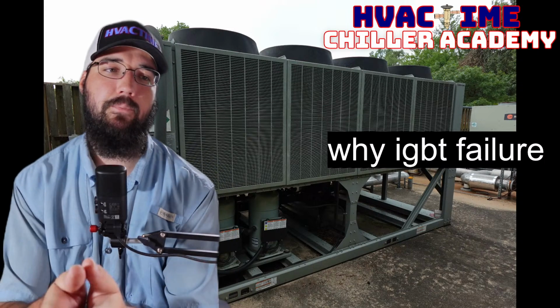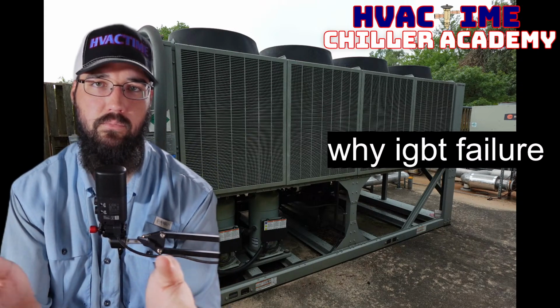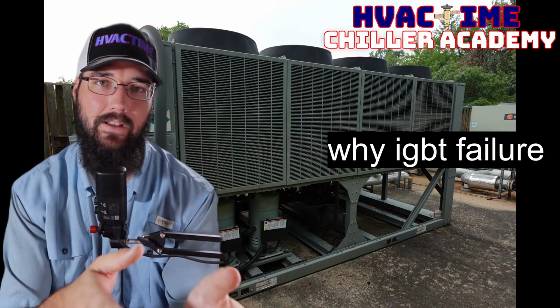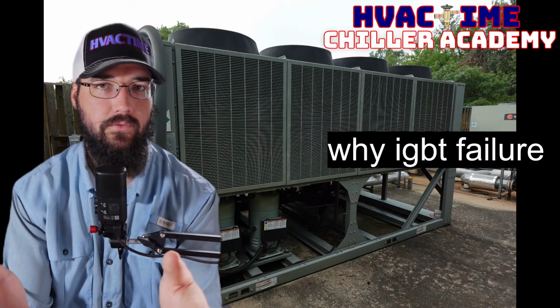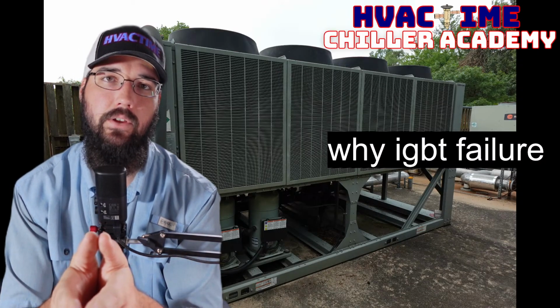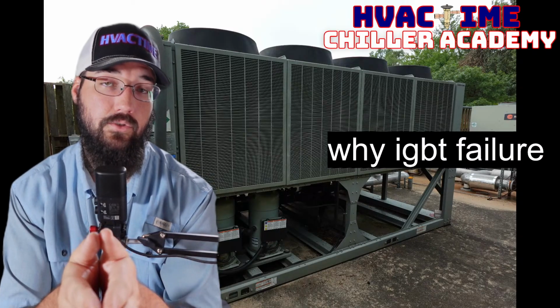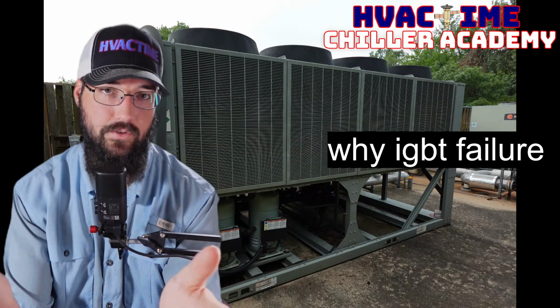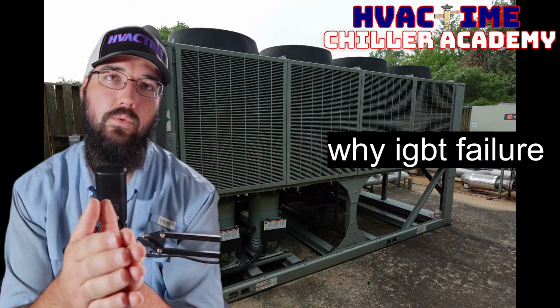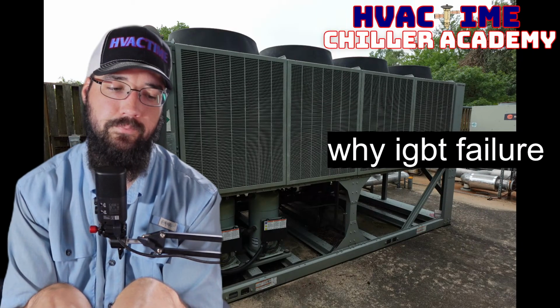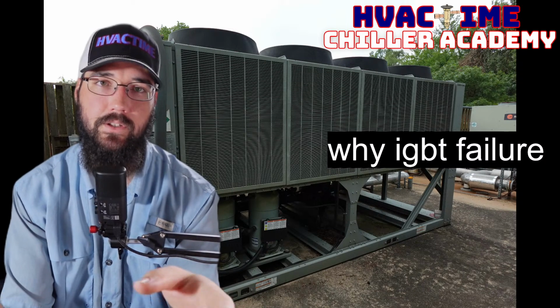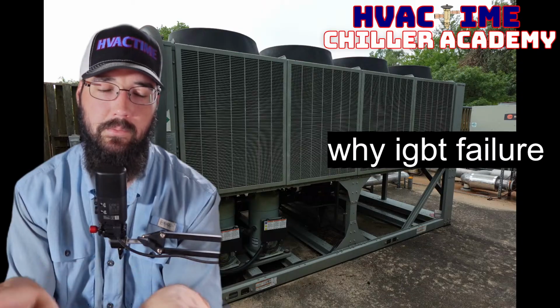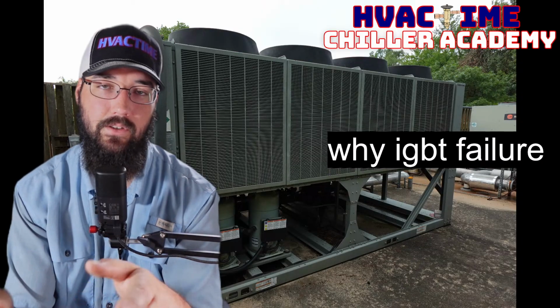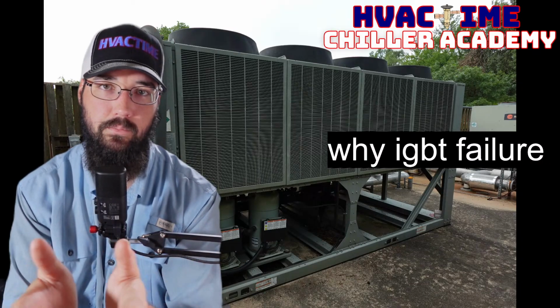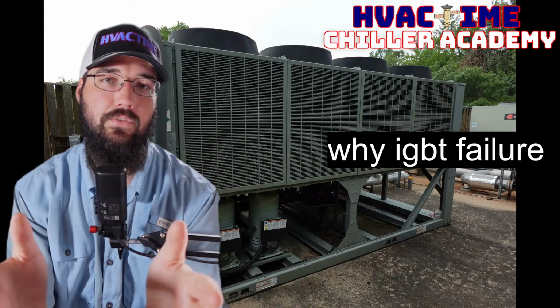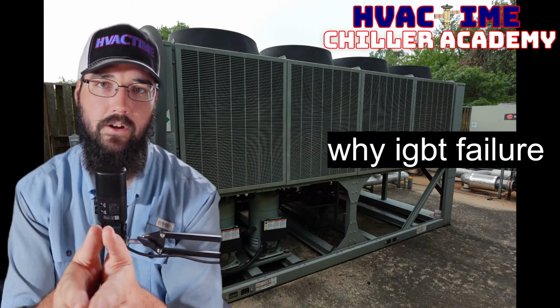Some things I would add to that. Keep in mind, IGBTs can be used as both an inverter and a rectifier. So in a lot of drive technology, like variable speed drives, we have historically used SCRs, silicon controlled rectifiers, hence the rectification. We've used those rectifiers as our rectification circuit to get our positive and negative DC bus. And if somebody wants to dive into this on a deeper scale, you're more than welcome to ask the question. I can do a whole bit on just VFDs, VSD theory in general, and I can talk it out here.